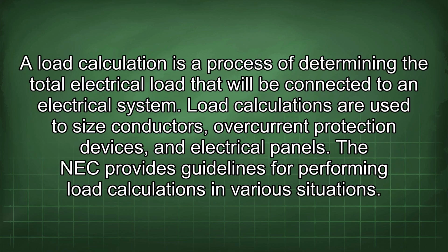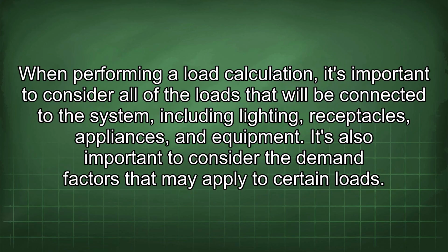A load calculation is a process of determining the total electrical load that will be connected to an electrical system. Load calculations are used to size conductors, overcurrent protection devices, and electrical panels. The NEC provides guidelines for performing load calculations in various situations. When performing a load calculation, it's important to consider all of the loads that will be connected to the system, including lighting, receptacles, appliances, and equipment. It's also important to consider the demand factors that may apply to certain loads.